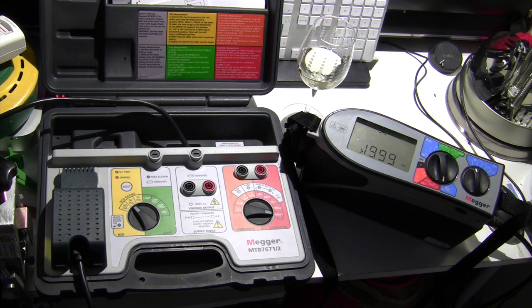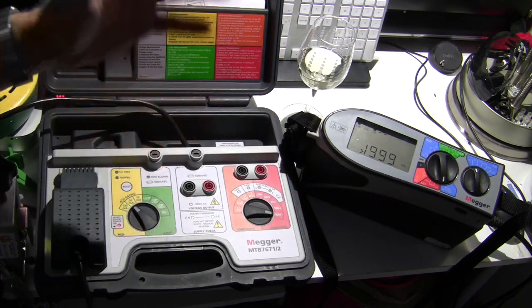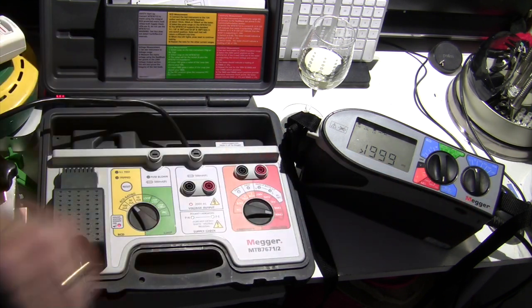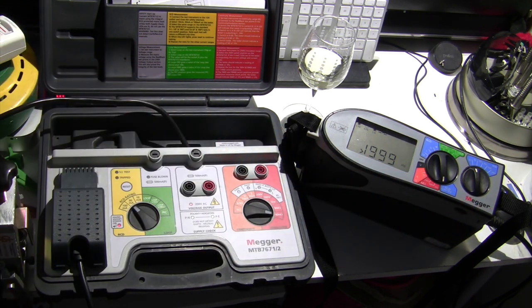Marvellous. Super. I'm not going to do the 100 milliamp test because obviously it's all the same stuff again. This tester does actually do 300, 500 and 1000 milliamps. The check tester does not, so I won't be able to test those ranges on this device, but I'm not too fussed about that because I can't remember the last time I tested an RCD above 100 milliamps anyway, so I won't worry too much about that until the time comes.